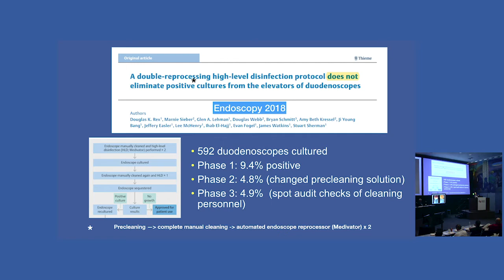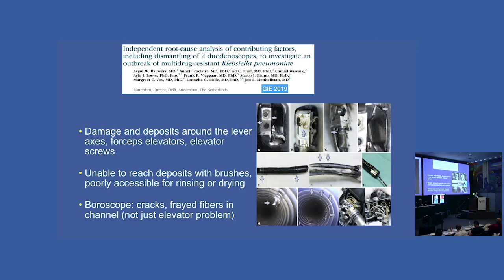This is a study from Holland, and it showed that there are damage and deposits around the lever axes, forceps elevator, the elevator screws. They were unable to reach many of these deposits with brushes, and they were poorly accessible for rinsing and drying. But what's really interesting is if you look at the boroscope picture, that's where you're passing something like a spyglass through the working channel, and they're seeing cracks in the working channel, and they're seeing frayed fibers in the channel. So it's not just an elevator problem.